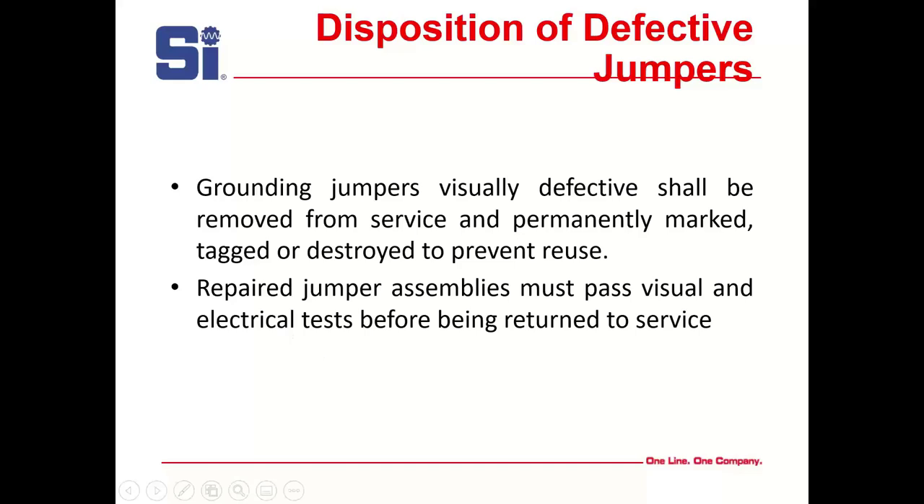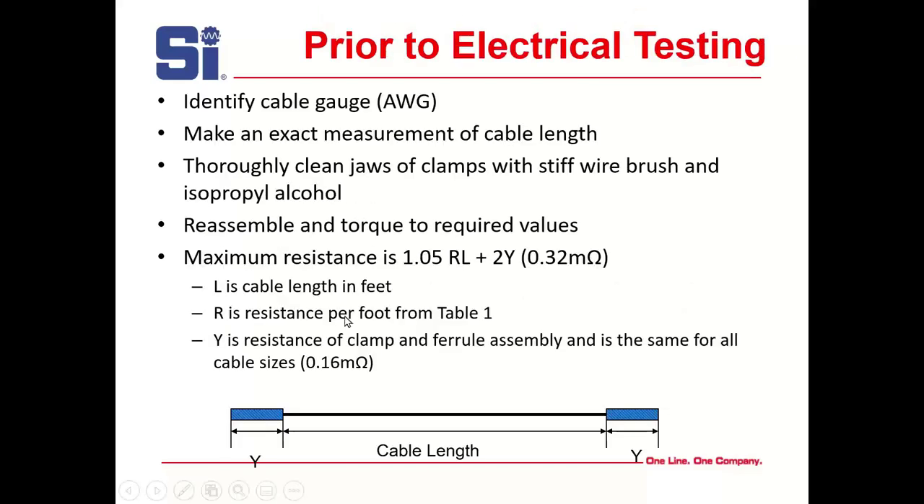Prior to electrical testing, identify the cable gauge, make an exact measurement of cable length, and clean the clamp with a stiff wire brush and isopropanol. Reassemble and torque to required values. Maximum resistance is calculated as 1.05 × R × L, where R is resistance per foot from the table and L is cable length, plus 2Y where Y is the resistance of the clamp and ferrule assembly — the same for all cable sizes — (0.16 milliohms).